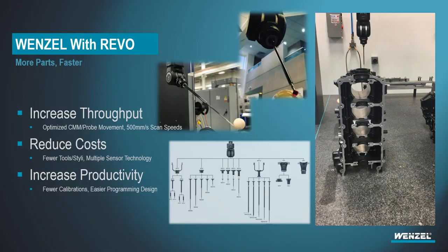Final benefit here before we move on: the Revo is a multi-probing system. From left to right on this graphic, you can see the surface finish probe to the far left. With a quick rack change, you can be doing surface finish inspection on any of your parts with the Revo access. You have the 5-axis scanning system, RSP2, that you've seen here on the engine block. And then you have an RSP3 scanning system, which really allows for long reach systems. It functions more like a traditional 3-axis scanning system. You can reach into parts up to 800 millimeters.